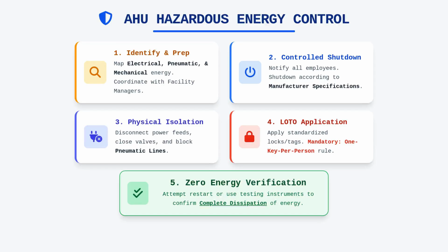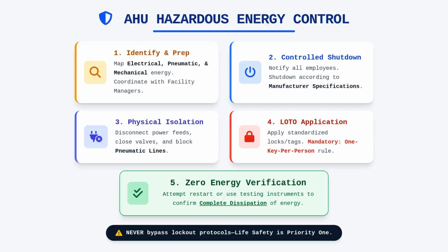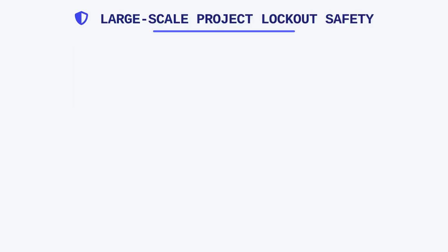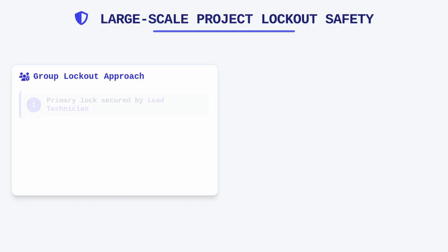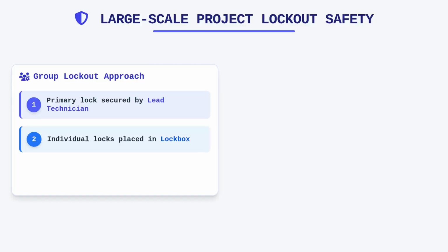Verification is the final step in this sequence, where you must attempt to restart the equipment or use testing instruments to confirm that the energy has indeed been dissipated and the system is truly de-energized. When dealing with large-scale projects, you will often encounter complex systems that necessitate a group lockout approach to maintain safety across multiple team members. In these scenarios, a primary lock is secured by the lead technician, or a lockbox is utilized where every team member places their individual lock to ensure the system cannot be energized until every person has finished their specific task.